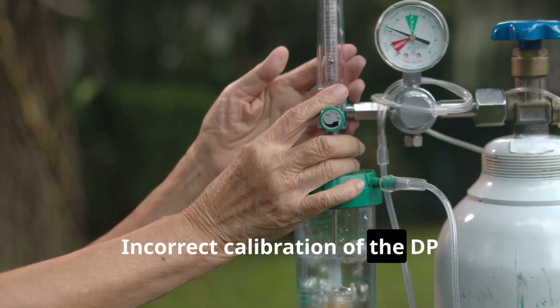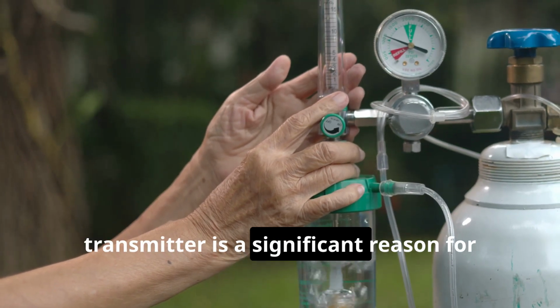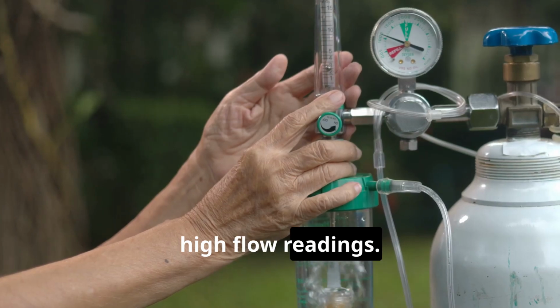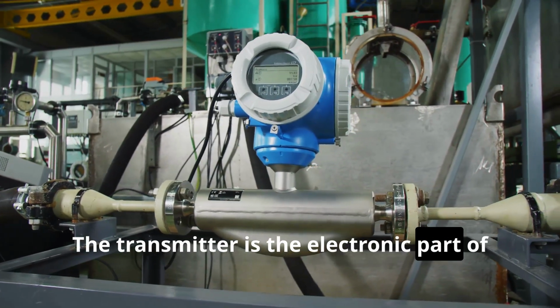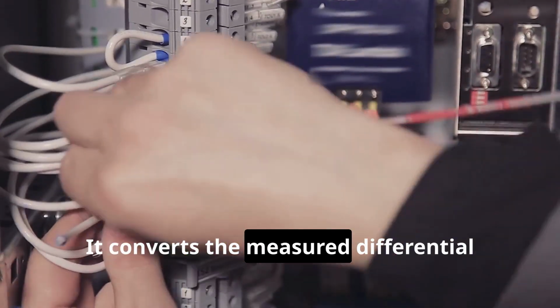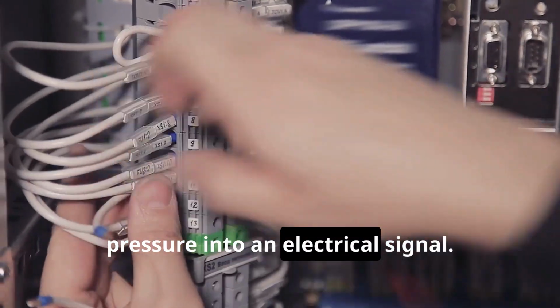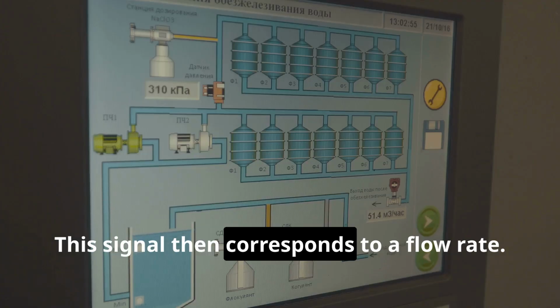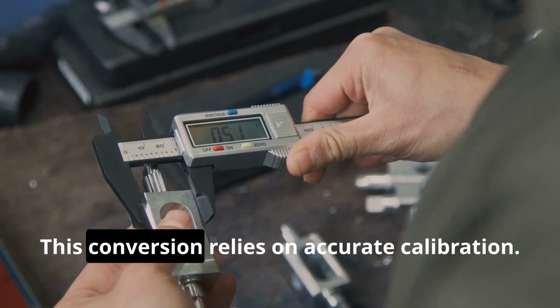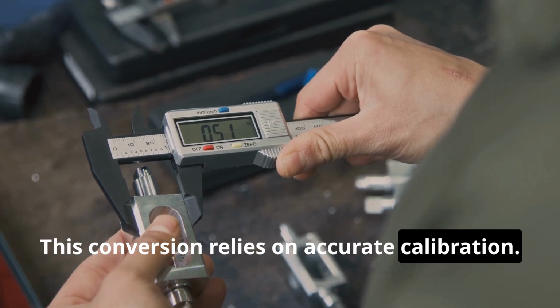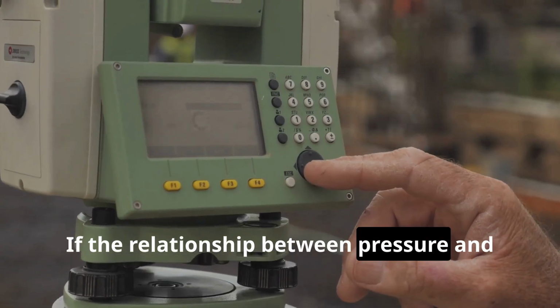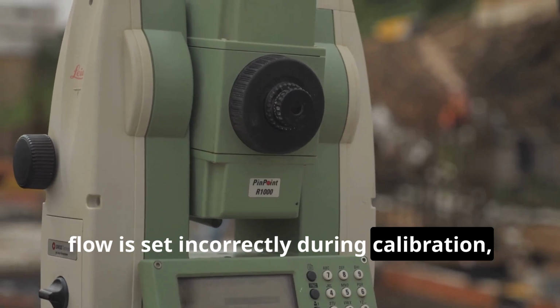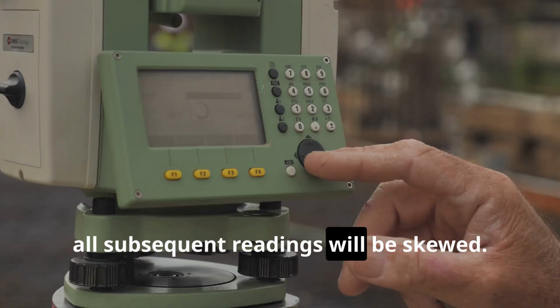Incorrect calibration of the DP transmitter is a significant reason for high flow readings. The transmitter is the electronic part of the meter. It converts the measured differential pressure into an electrical signal. This signal then corresponds to a flow rate. This conversion relies on accurate calibration. If the relationship between pressure and flow is set incorrectly during calibration, all subsequent readings will be skewed.